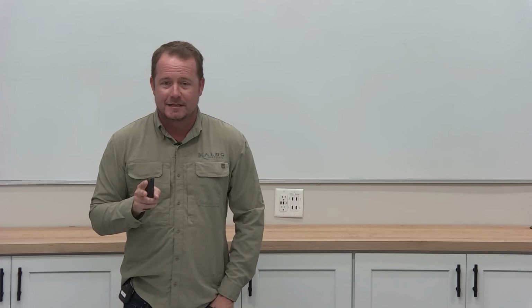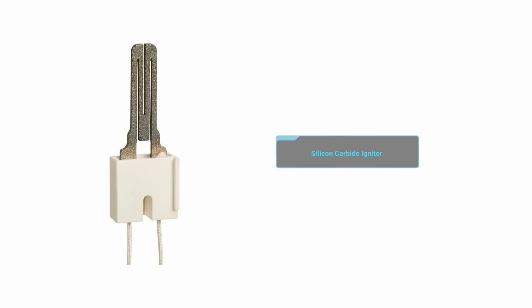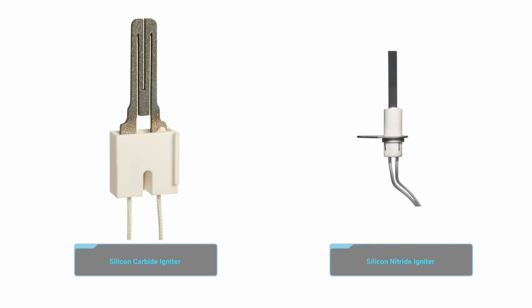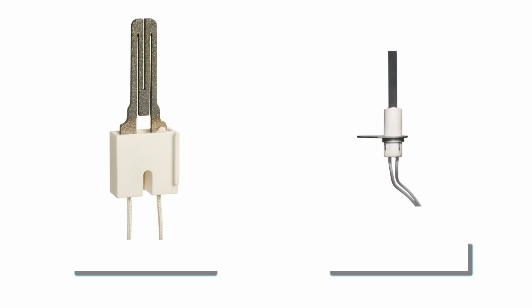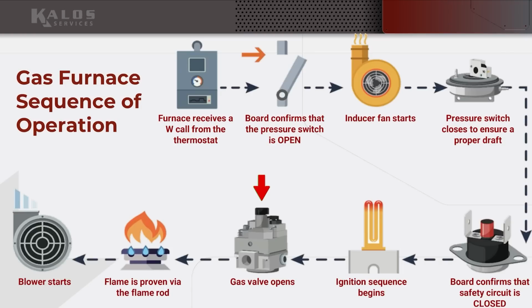There are two different common types of igniters. The old ones are silicon carbide. The new ones are silicon nitride. As far as you're concerned, the only difference is they look a lot different. The old school ones look like this, like an old oven coil. The newer ones are just like a little stick or a little round rod. Then the gas valve opens once the timing is done, and it's actually going to dump gas over that igniter.